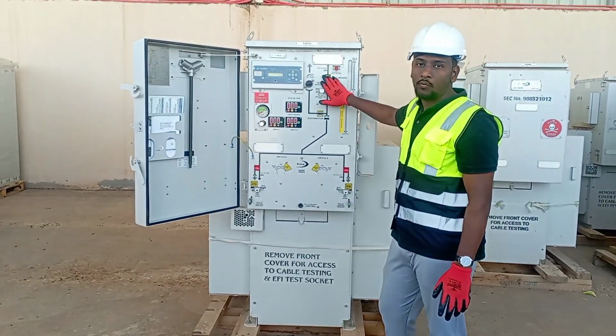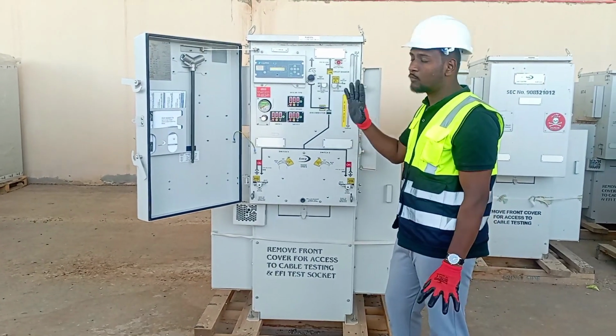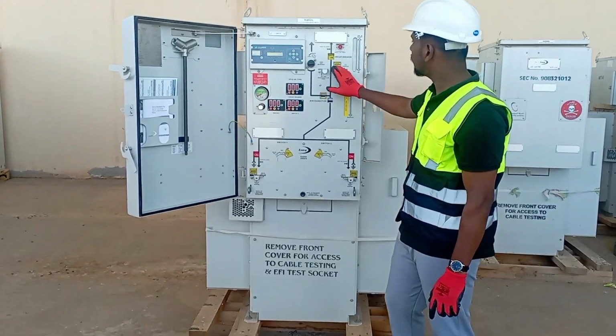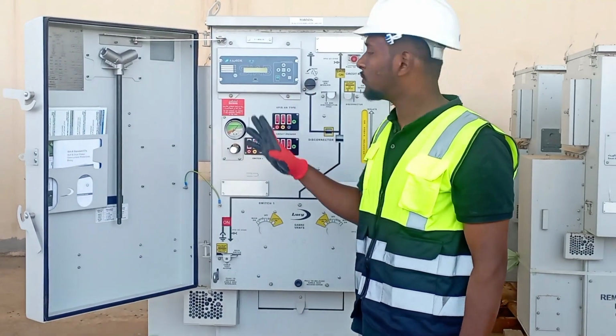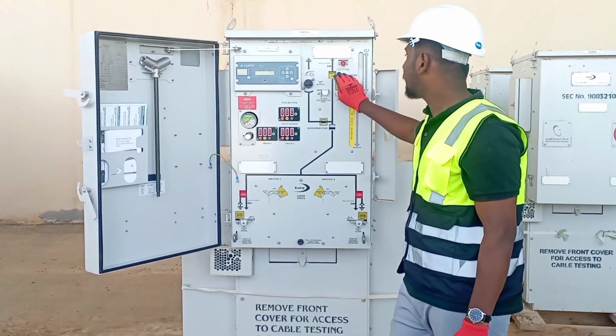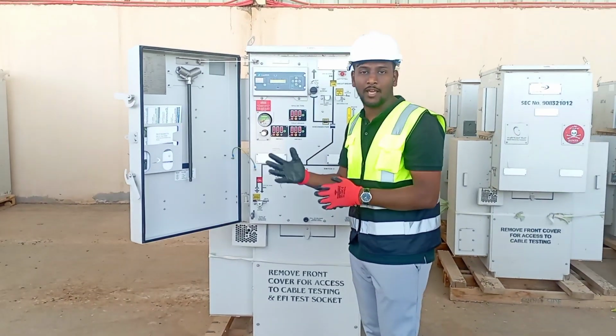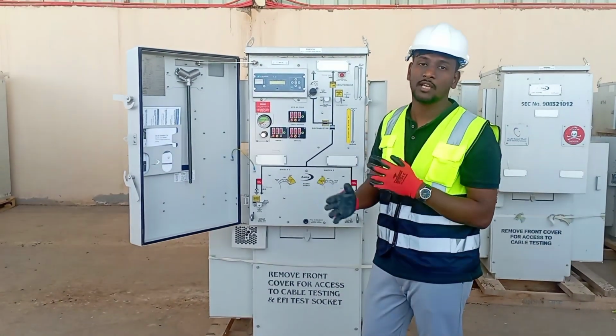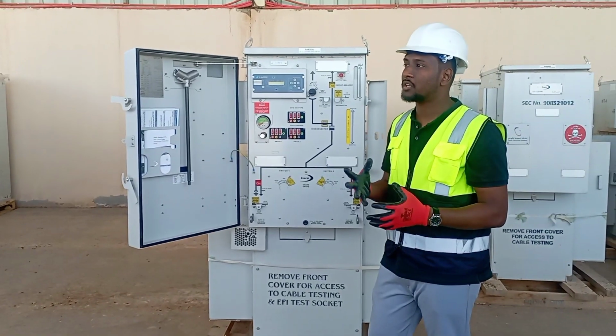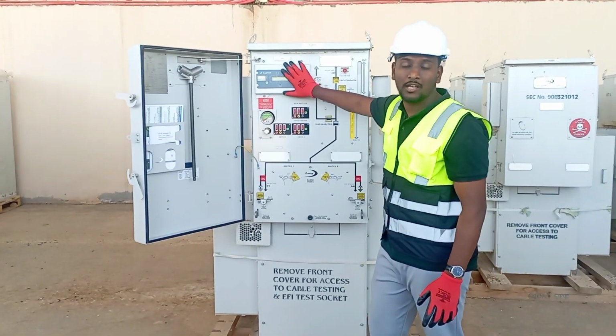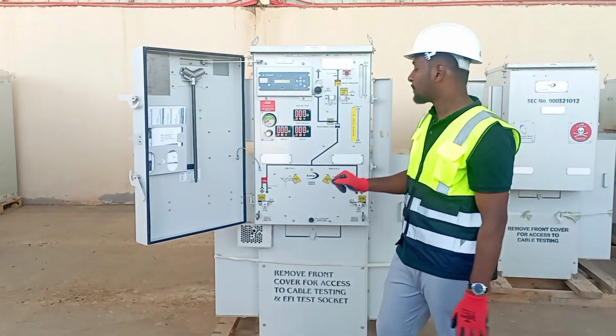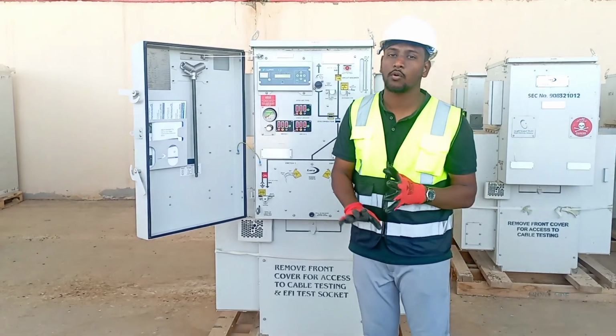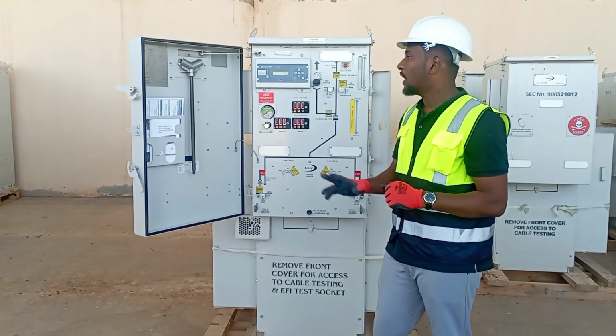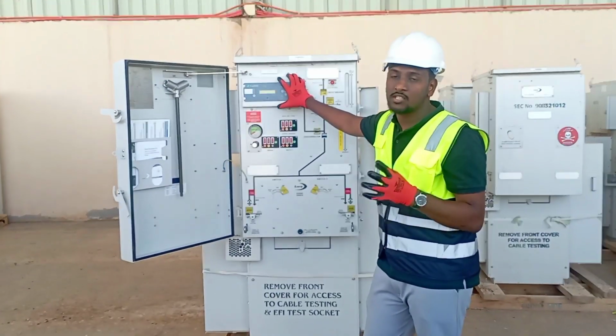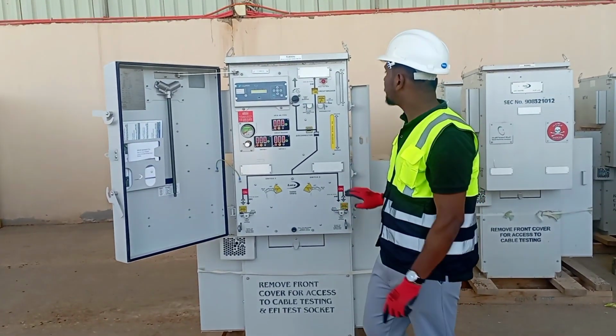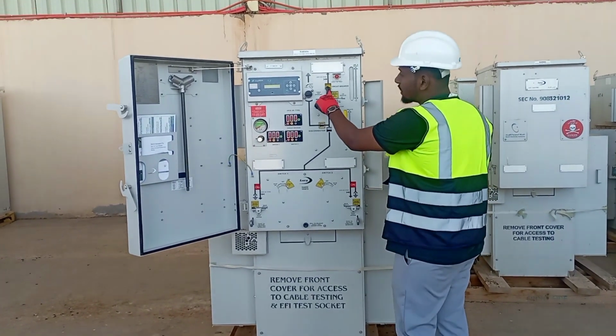As I told you before, this T off is always connected to transformer. Mostly this one connected to transformer. Okay, so why are we connecting this T off to transformers? Because this relay is connected to this T off, and if on the HT side customers have any over voltage or any mistakes, the relay will help to trip the T off automatically. And the T off always consists of CT, current transformer, and this relay is working by using the supply taken from the current transformers. Okay, and now we can see this T off is in earth position.